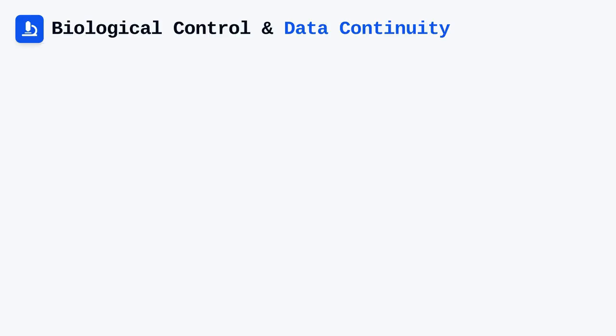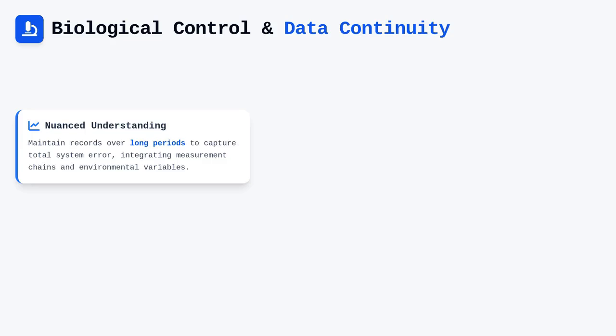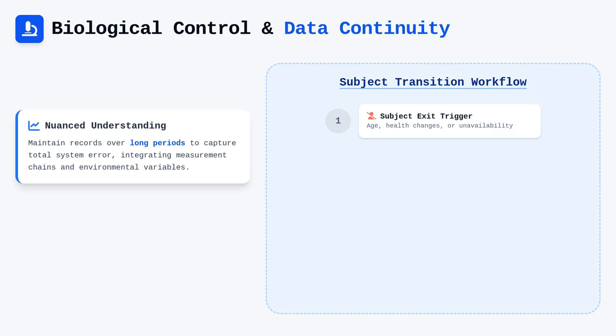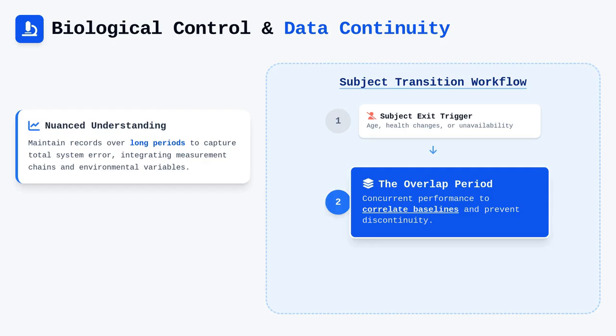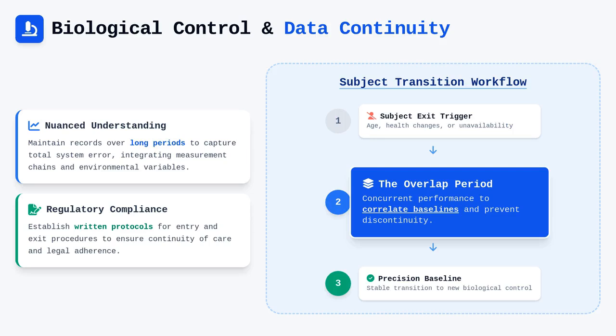Maintaining these records over long periods allows for a more nuanced understanding of your system's total error, encompassing both the measurement chain and the environmental variables. When a biological subject reaches a point where they are no longer available or their pulmonary function changes due to age or health, transitioning to a new subject requires an overlap period. During this transition, you should have the new subject perform alongside the existing one to correlate their baselines, ensuring that your quality control data does not suffer a sudden discontinuity. Establishing a written protocol for these exit and entry procedures is essential for regulatory compliance and continuity of care.